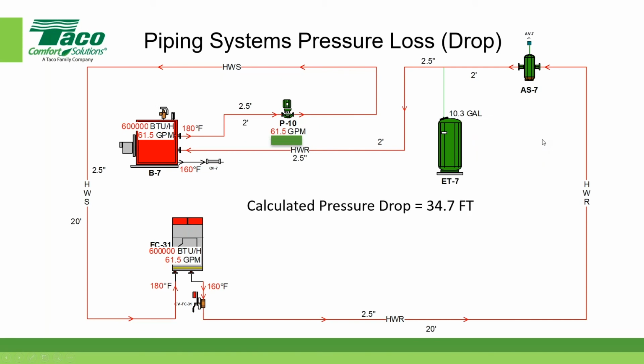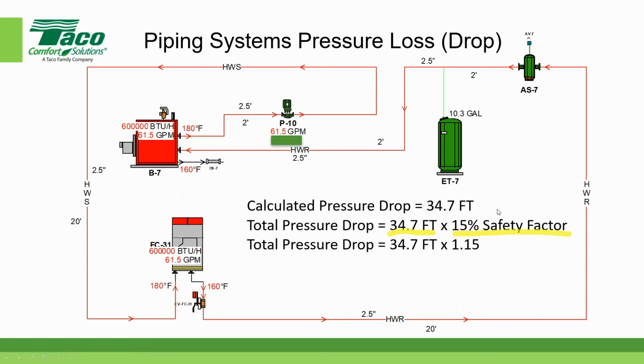So now we did the calculated pressure drop of approximately 34.7 feet. And then I have a second line here, which I call the total pressure drop. So the total pressure drop of the system is the calculated pressure drop, that's this value here, let's highlight this, that 34.7 feet times a safety factor. And in my case, I selected a safety factor of 15%. So that means my total pressure drop in my system is 34.7 times 1.15. If you do the actual arithmetic, it came out to about 39.9, and I rounded it off to 40 feet.